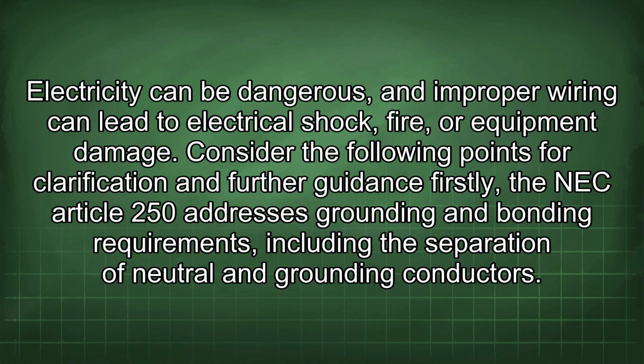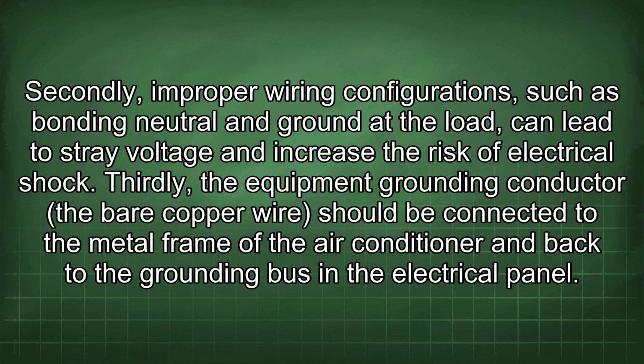Firstly, the NEC Article 250 addresses grounding and bonding requirements, including the separation of neutral and grounding conductors. Secondly, improper wiring configurations, such as bonding neutral and ground at the load, can lead to stray voltage and increase the risk of electrical shock.